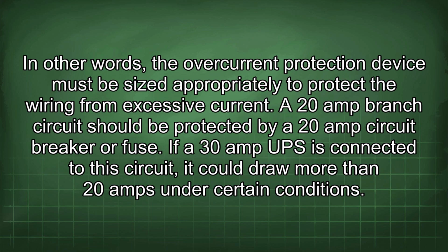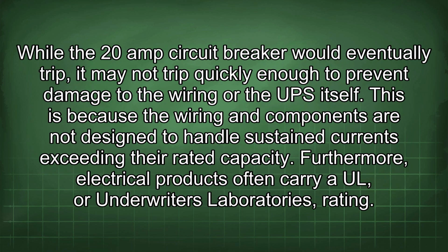If a 30 amp UPS is connected to this circuit, it could draw more than 20 amps under certain conditions. While the 20 amp circuit breaker would eventually trip, it may not trip quickly enough to prevent damage to the wiring or the UPS itself. This is because the wiring and components are not designed to handle sustained currents exceeding their rated capacity.